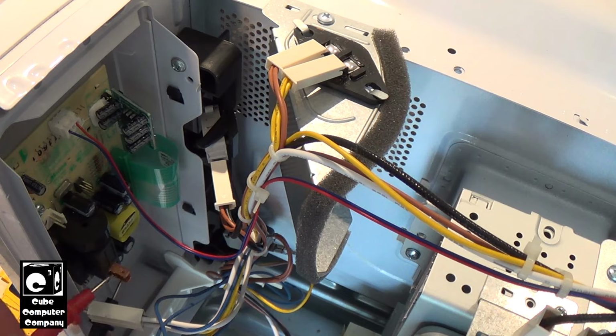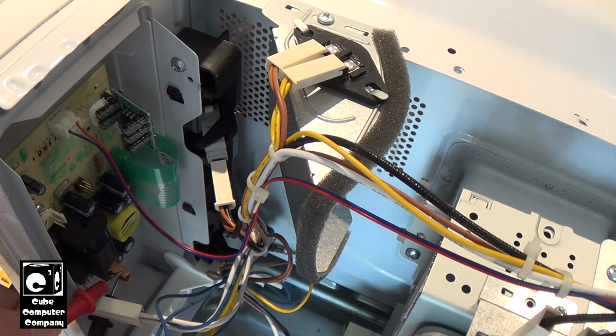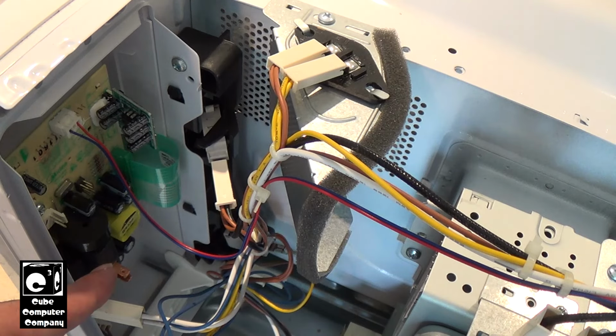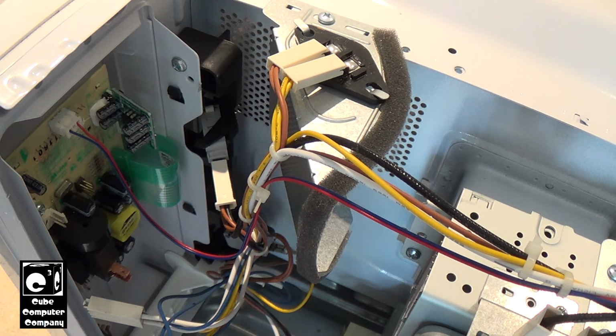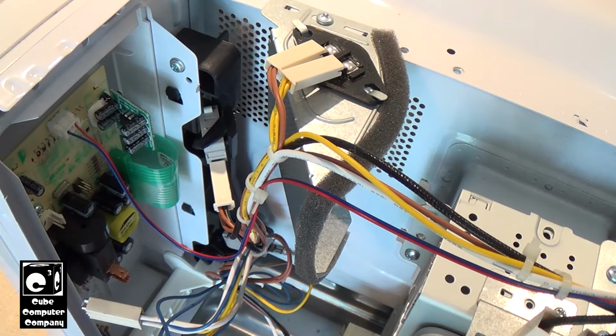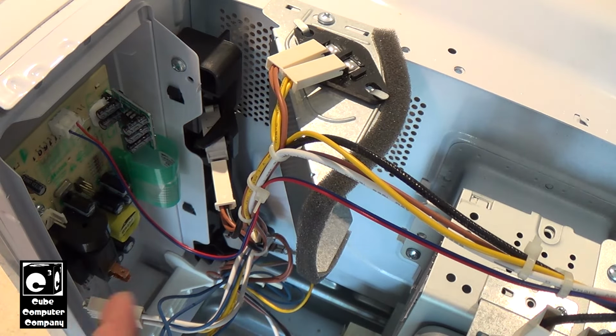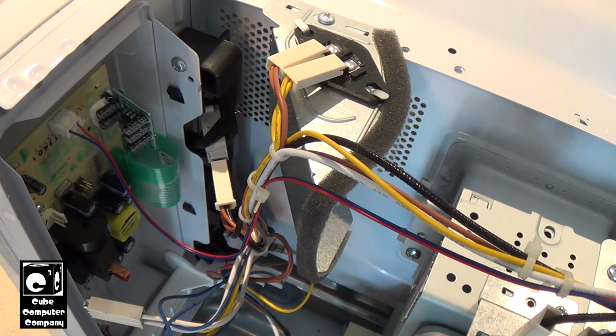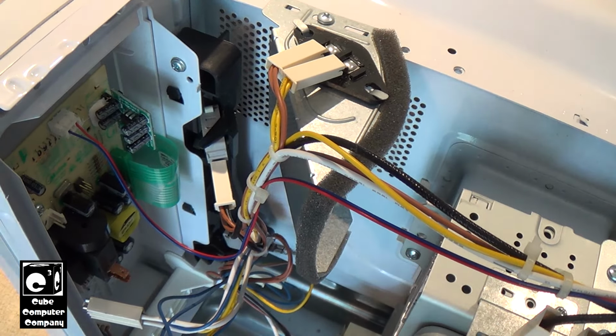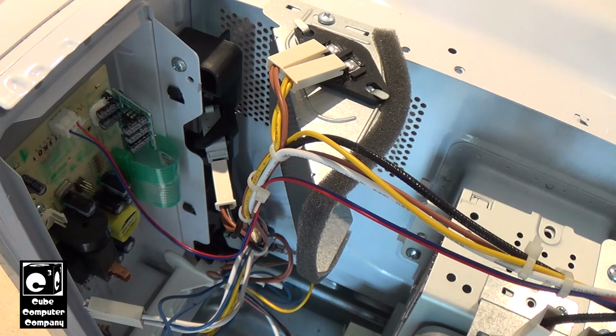So I'll test this relay again, and it's open. Alright, so what could happen here is this relay might be failing intermittently, meaning at times it sticks and remains in the closed position, but after a bump or whatever, or me, for example, trying to yank these wires out of it, might have opened it. It made it appear that it's working okay.